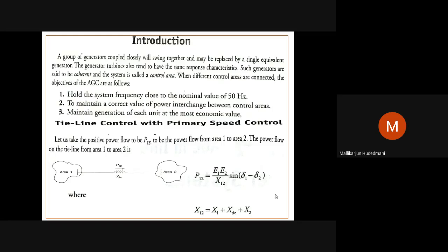In that perspective, the corporations which are interconnected need to install tie lines. Tie lines are the transmission infrastructure between the energy corporations like A, B, C, etc. Basically, they are meant for the exchange of power. If the corporation possesses excess power, it can trade to the neighbor. If it finds a deficit of generation due to any reason, maybe generators on maintenance, or due to some sudden fault a certain generator area is disconnected, you would like to meet your requirement and you can borrow the power. These infrastructures help at that time.